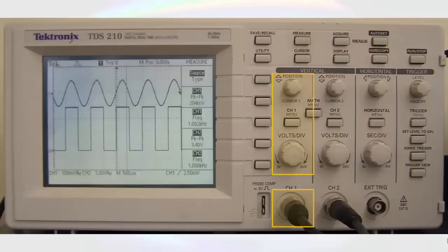Channel 1 is controlled by these three controls. Channel 2 is controlled by these controls. We can adjust the position of the wave on the screen, which refers to the point indicated by the numbers 1 and 2 on the left-hand side of the screen. For each of these waves, this is the point that is considered as 0 volts. The volts represented by each division is controlled by these two knobs. The left-hand knob controls channel 1, and the right-hand knob controls channel 2. The volts per division can be set independently for each channel. The third set of controls adjusts the horizontal axis, or the time axis. We can adjust the time equals 0 point and seconds per division to look at different frequency signals.